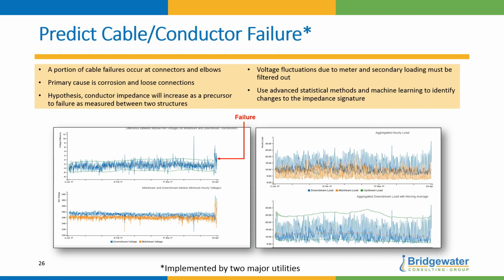So a portion of the failures are mechanical: corrosion, loose connections. Not all of them, especially underground, you'll get treeing in the insulation and stuff like that. Meters can't do anything about that, it's too high frequency. But if it's mechanical, can we predict an issue with an elbow or a connector? And the answer is, to a degree, yes.